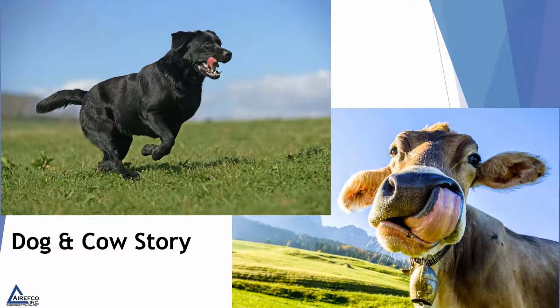Then there's the story of the dog and the cow. A couple of our service managers have gotten calls where there's been a short on an outdoor unit, and it turns out a dog or a cow has been chewing on the thermostat wires leading to the outdoor unit. This is another area to check if the homeowner has pets, or if it's on a farm where cows can get close to the outdoor unit. We've seen this numerous times, where the outdoor thermostat wire has been chewed through, causing either a short or causing the outdoor unit not to operate.